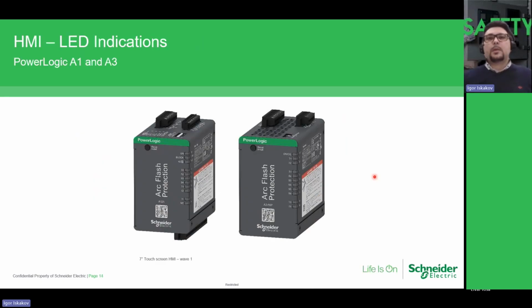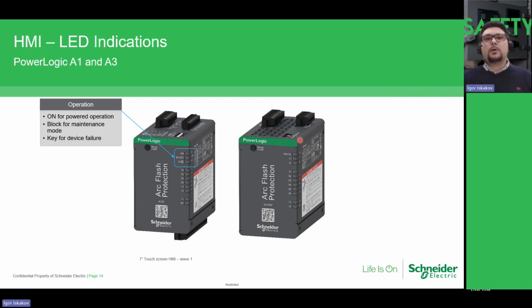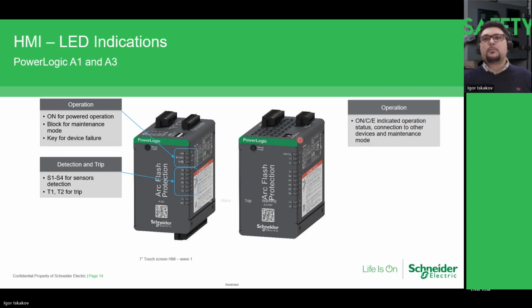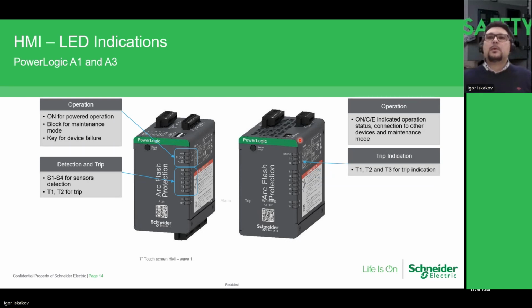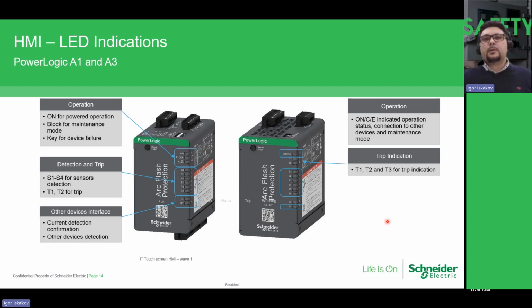So here are the units, and you see here power on and operational, so you will see whether the device is active and whether the device is healthy or not. You see the sensors' status and the status of the trip contacts, and similar indications on the A3 device. You have the trip contacts here, which can be dedicated to different purposes by using different operational schemes. And you also have a watchdog contact for the system.